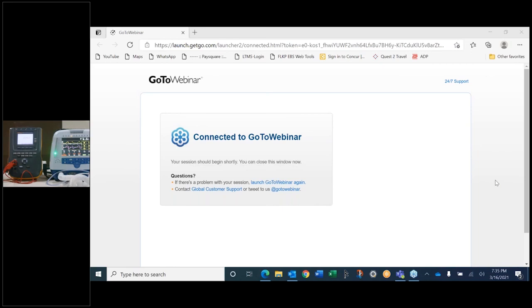Okay. Let us go. Actually, what we have right now today is a portable ventilator, which does not have an accessible ground point. So we are going to skip that and we do the touch current. And before going to that, the first part of the things yesterday we could not show.